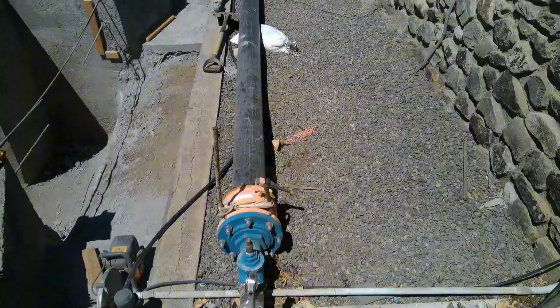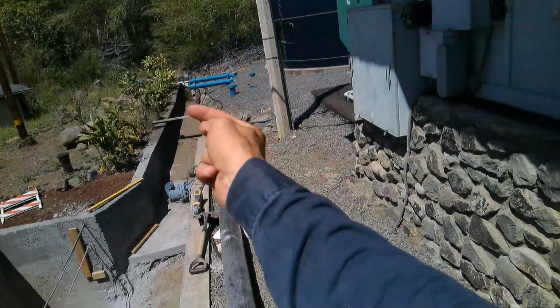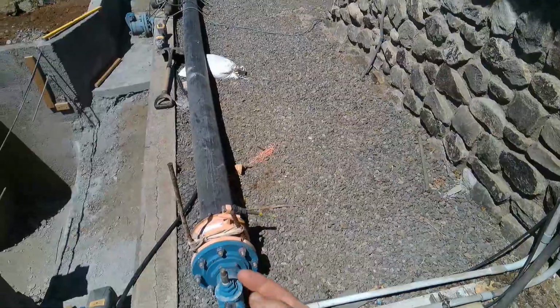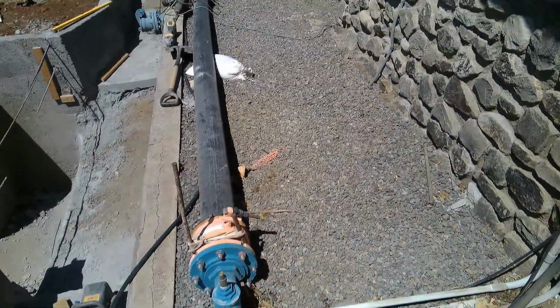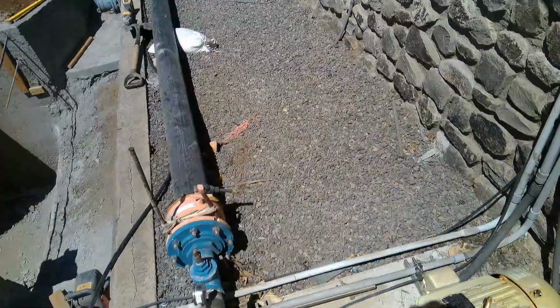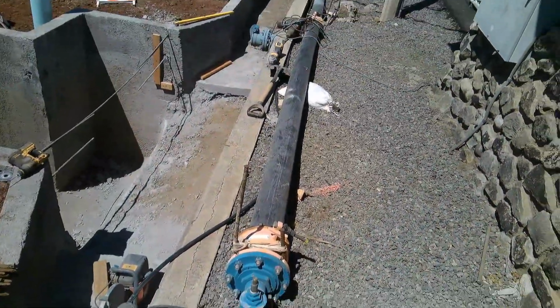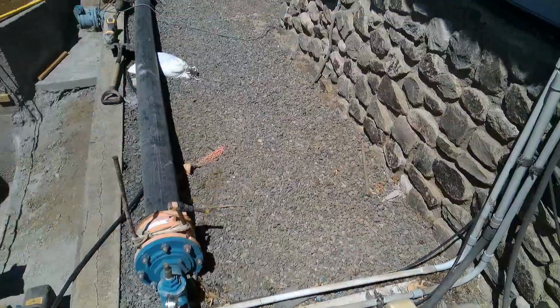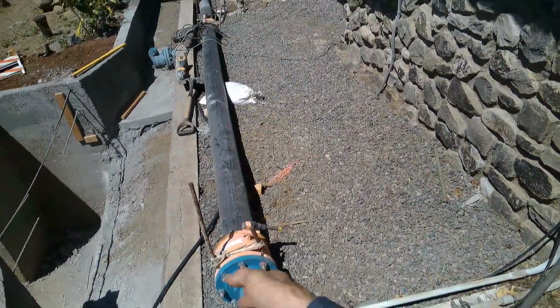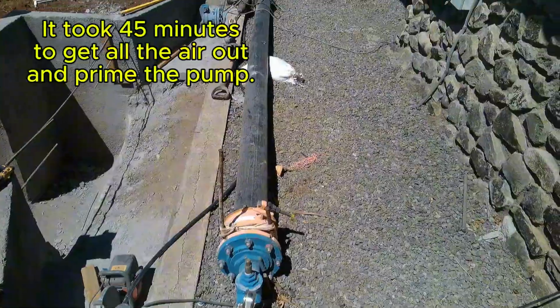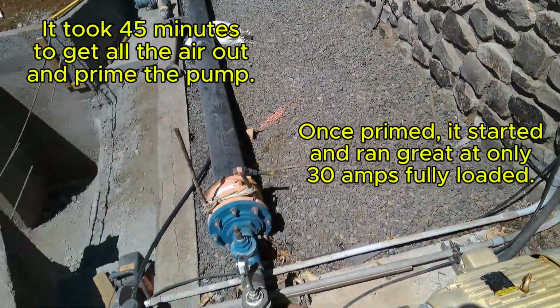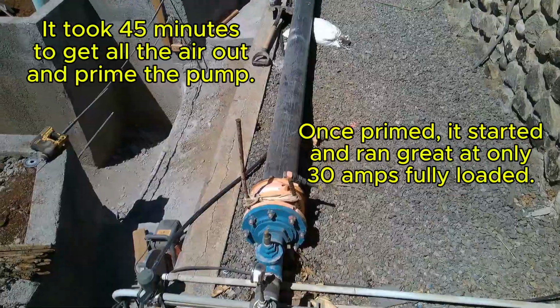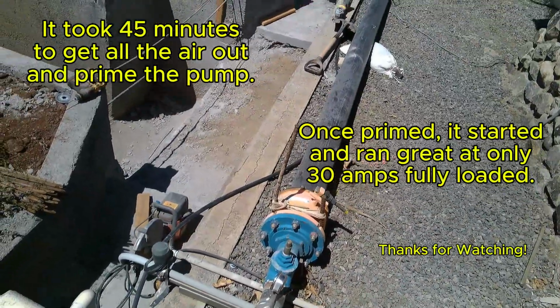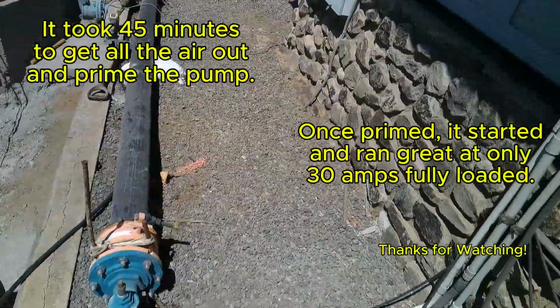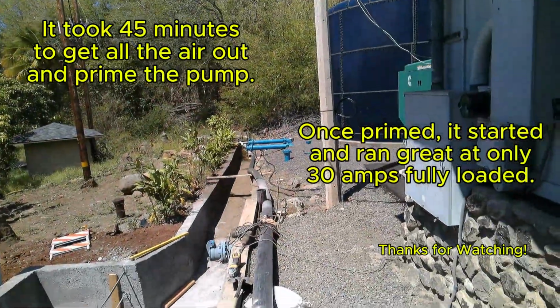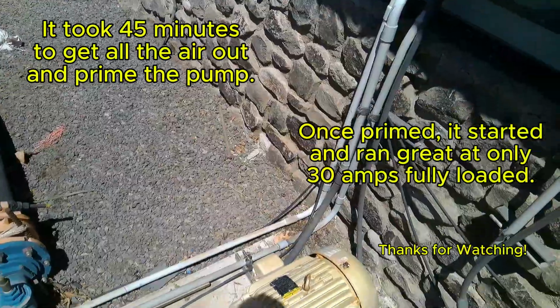So these guys don't have a check valve on this pump suction. This pump suction is a discharge from another pump. It's pulling it from a reservoir. And since there's no check valve, every time they turn it off and open this up, all the pipe gets air pulled into it. So now the only air release they have is this tiny little 1/4-inch bibcock, ballcock valve. So now we're bleeding all the air out there, and then we can start up the pump and get some run data.